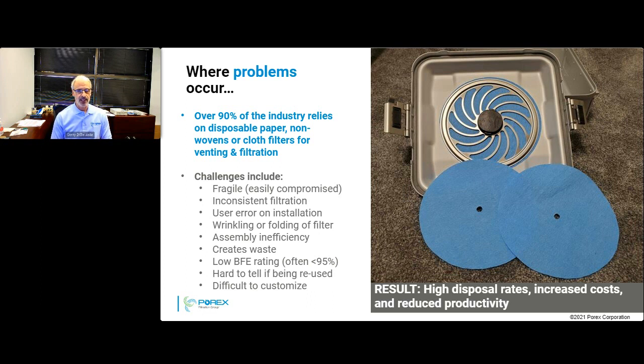Assembly inefficiencies. Like I mentioned earlier, every time these units are used, they have to be disassembled, and then that filter has to be removed and replaced. And one of the things that is critical is, how are you assured that the filter has been replaced? These are typically one-time use, and there are some that have an indicator, but most of them don't, to show that they've been used. And so, if there's no indicator to show that this has been used, how do you know that it's not being reused multiple times? These products really are not designed to be used more than once, and there are facilities that use them multiple times, and that seriously compromises potential patient health.